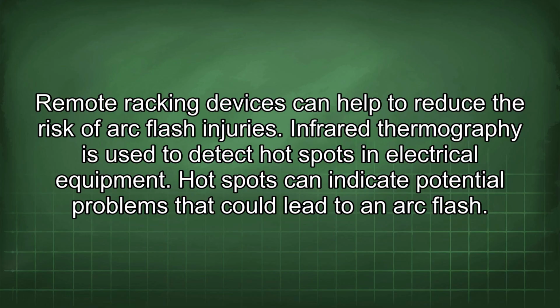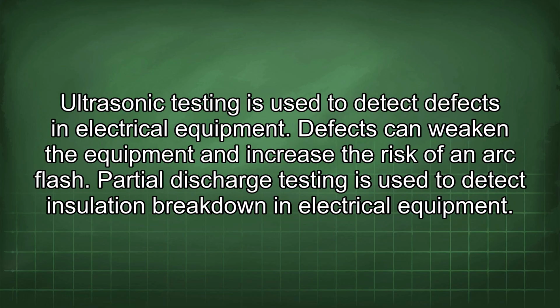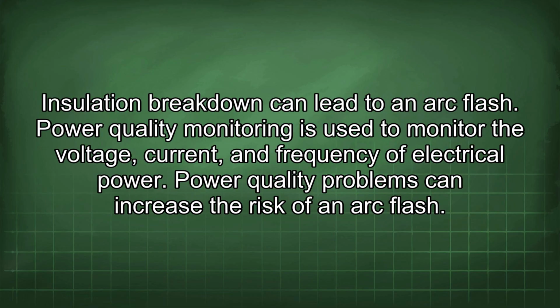Infrared thermography is used to detect hot spots in electrical equipment. Hot spots can indicate potential problems that could lead to an arc flash. Ultrasonic testing is used to detect defects in electrical equipment. Defects can weaken the equipment and increase the risk of an arc flash. Partial discharge testing is used to detect insulation breakdown in electrical equipment. Insulation breakdown can lead to an arc flash.